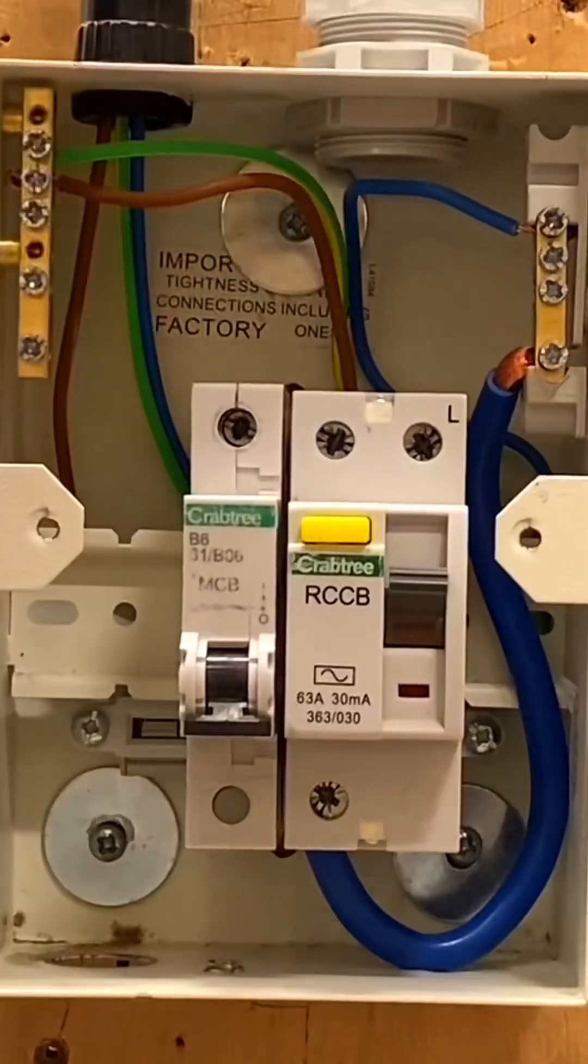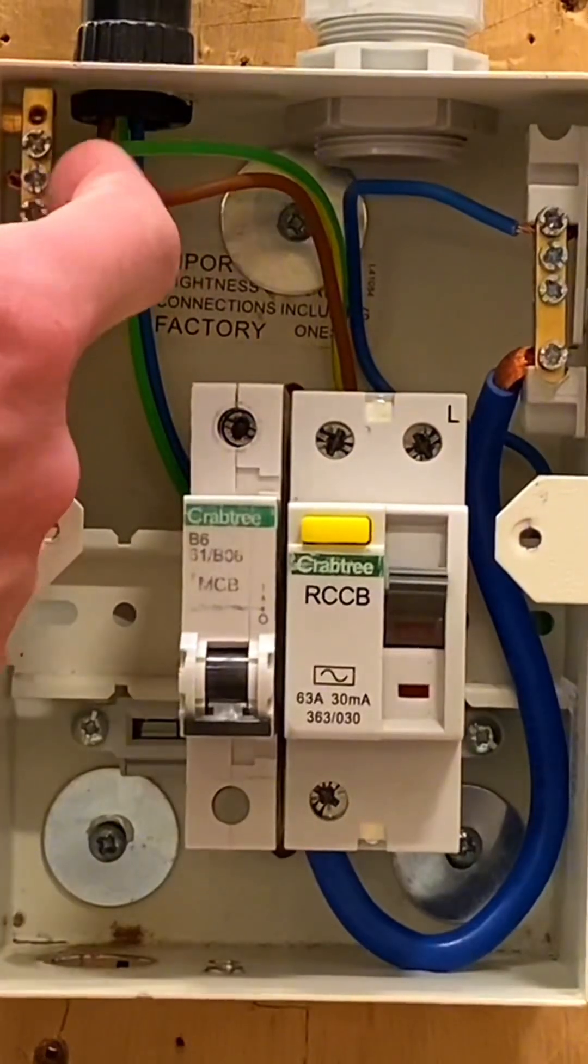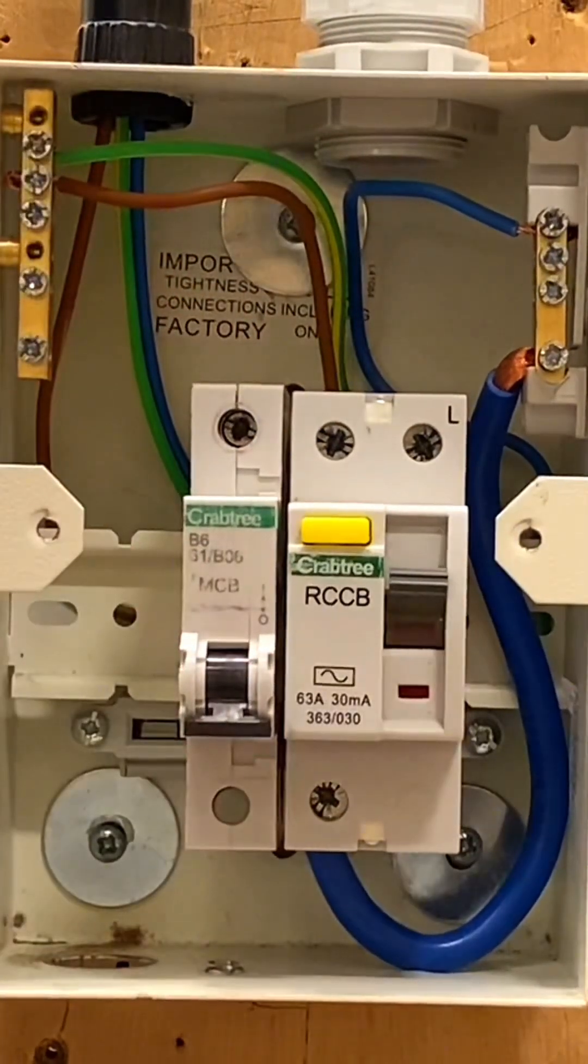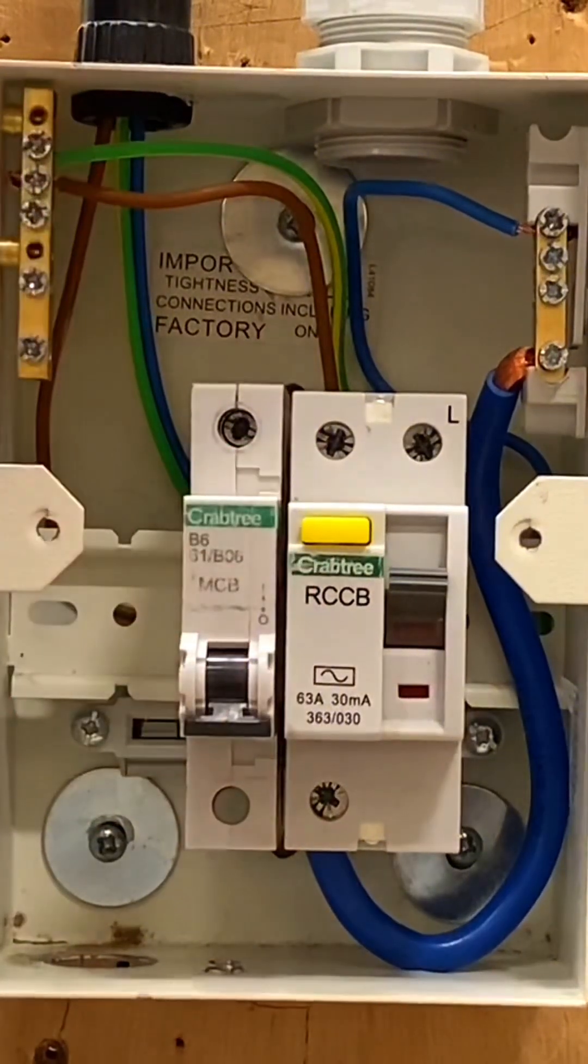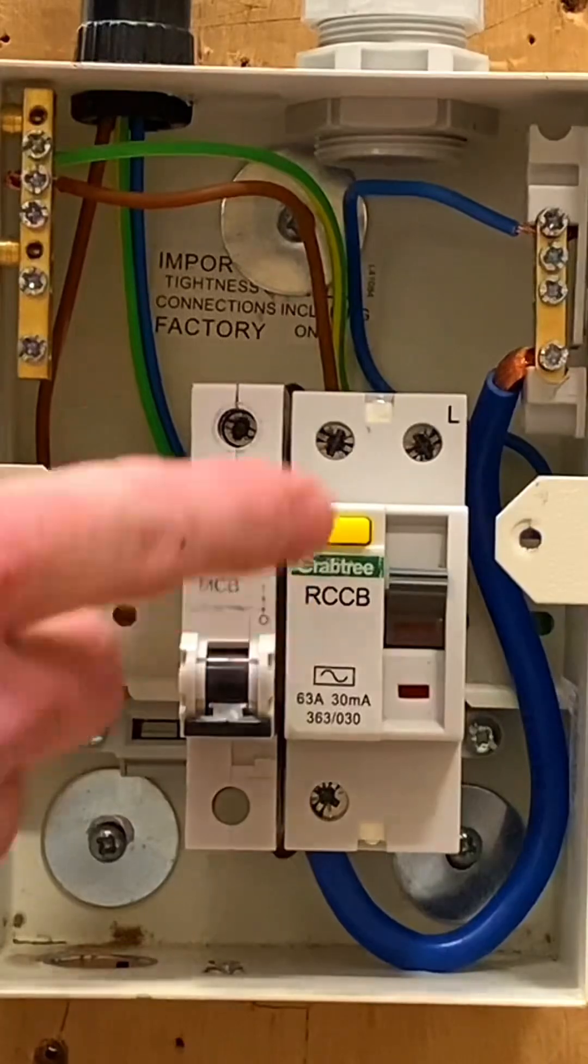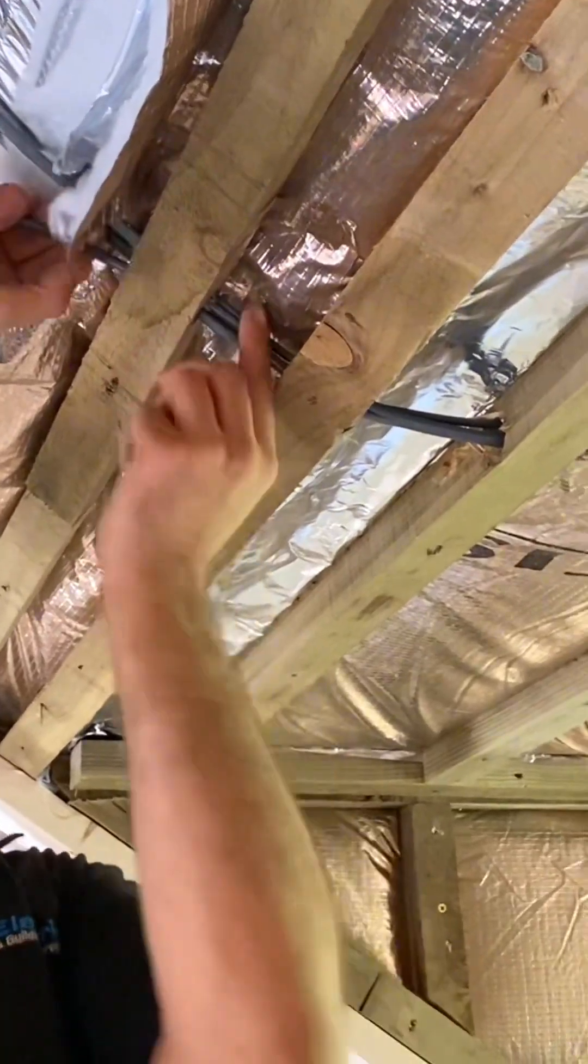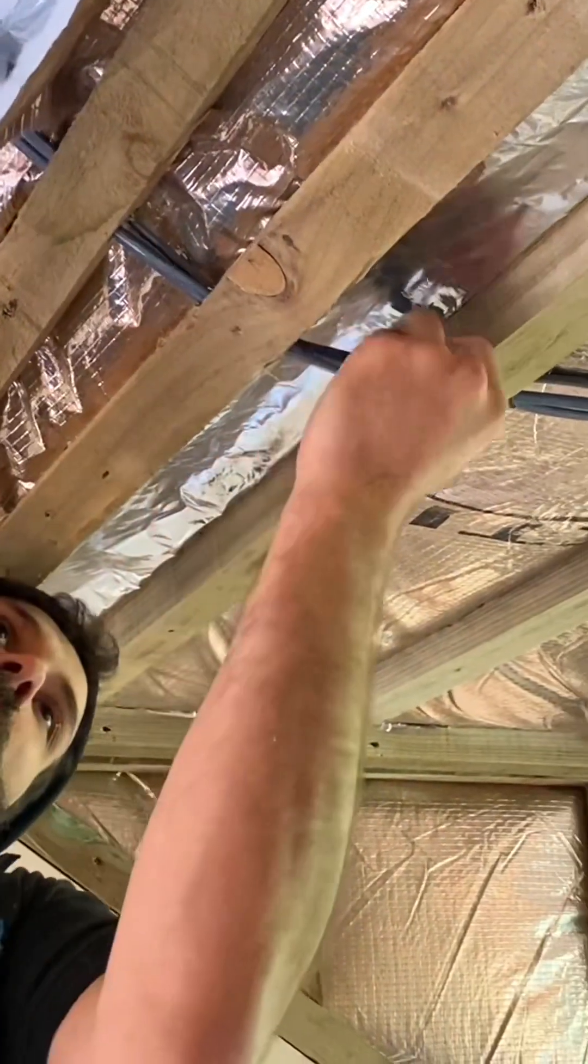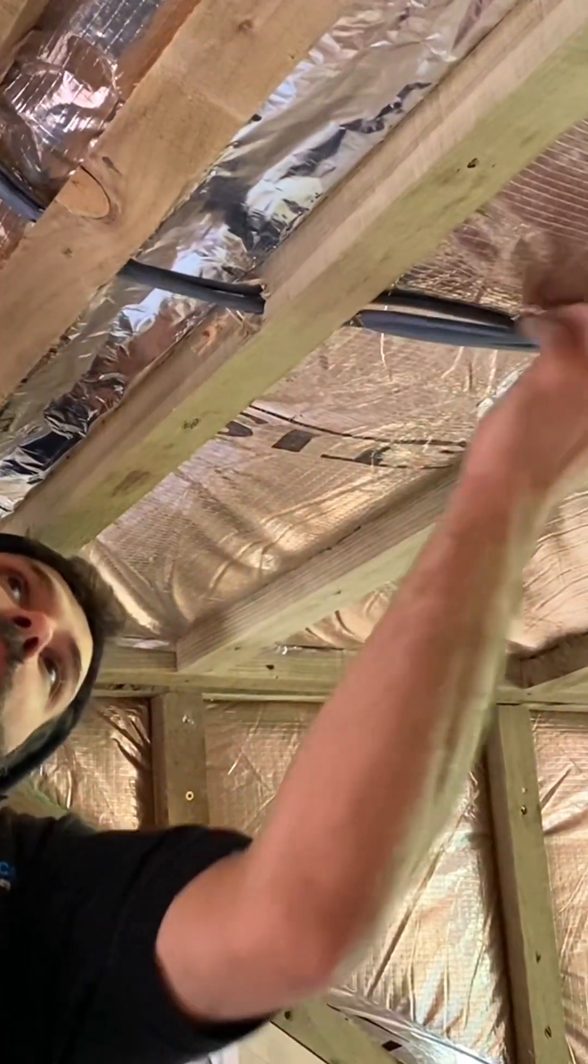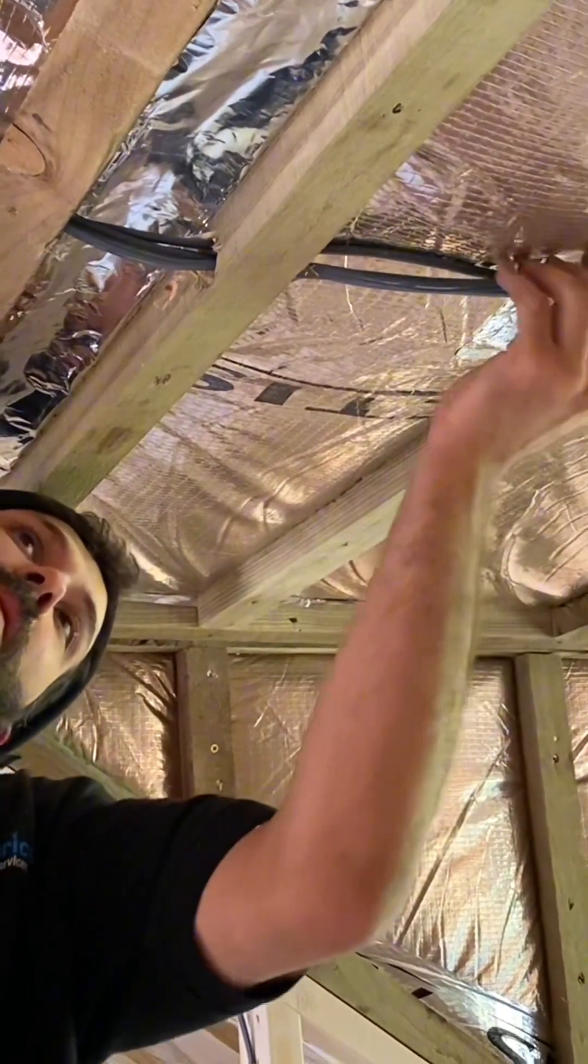I've linked the CPC and line conductor together by putting them in the earth bar. To recap for our learners, this lighting circuit didn't need an RCD rated at 30 milliamps and below because of how it's installed. However, domestic lighting circuits using PVC PVC twin and CPC cable absolutely needed RCD protection. This has just got it, so it doesn't hurt to have the RCD protection.